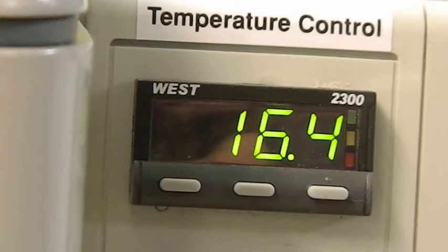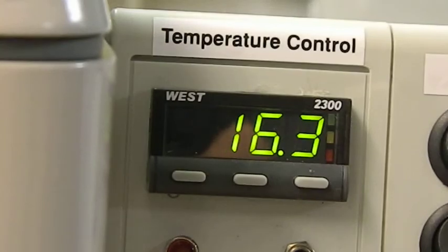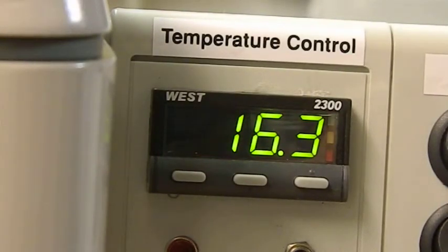Okay, let's get this back again. Okay, the controller is currently reading 16.3 degrees. This may seem low, but what we tend to do is we set them when we first switch the machine on. This gives us two opportunities to calibrate them while they're testing. One when they're running up to temperature and one when they're actually finally at temperature. It just gives us two chances to get them absolutely spot on rather than just one.